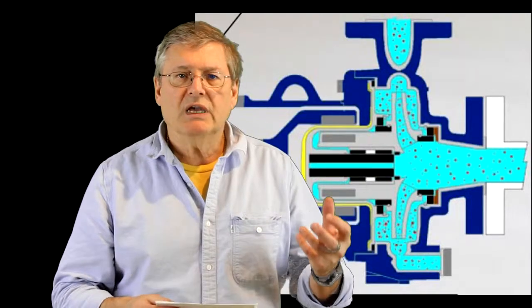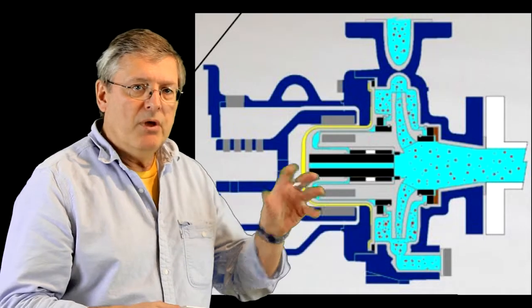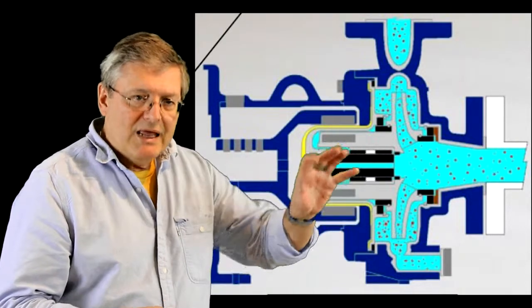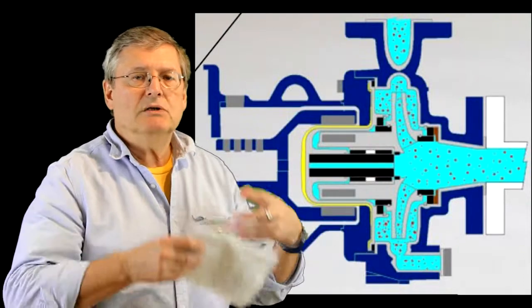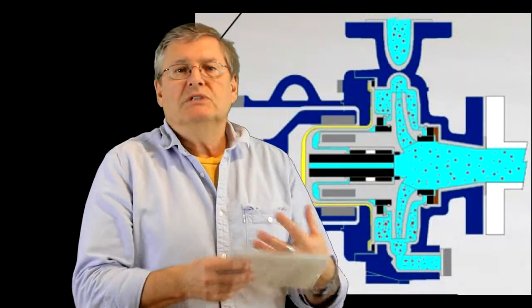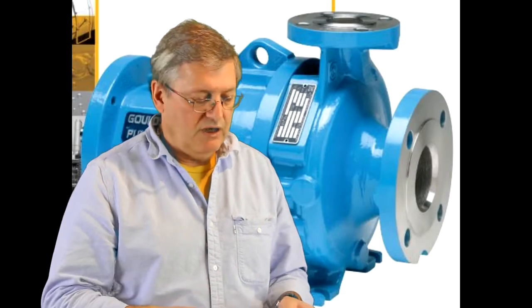The characteristic is that the drive is isolated from the pump by means of a magnetic driving arrangement. So it's driven through magnets, therefore there is no seal that could leak, making it more or less intrinsically safe.